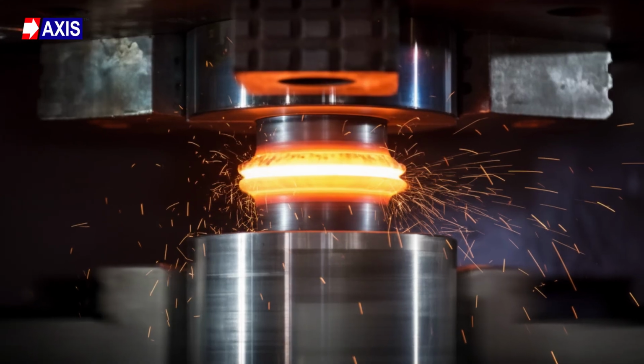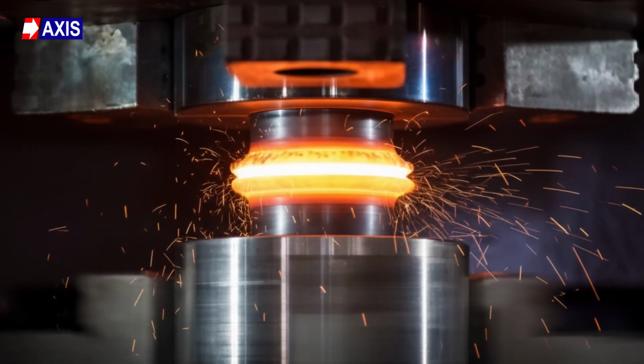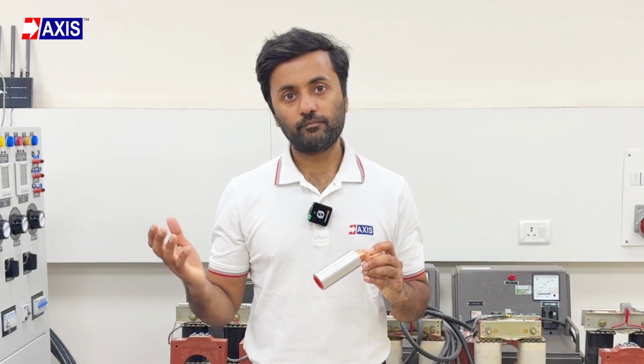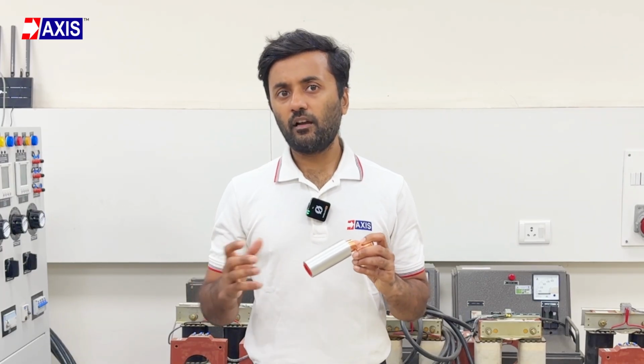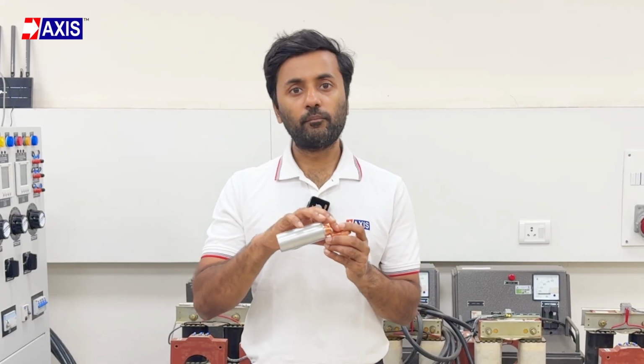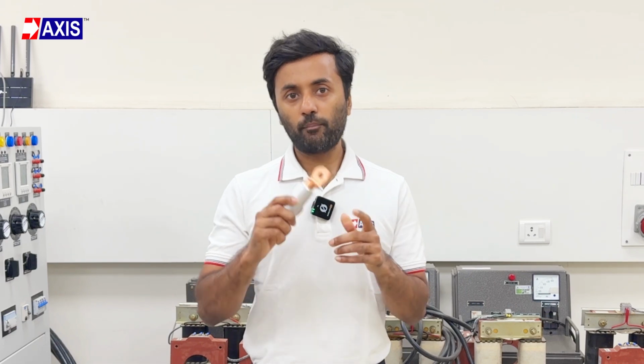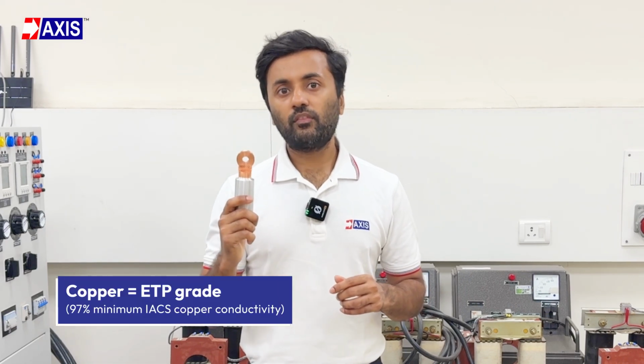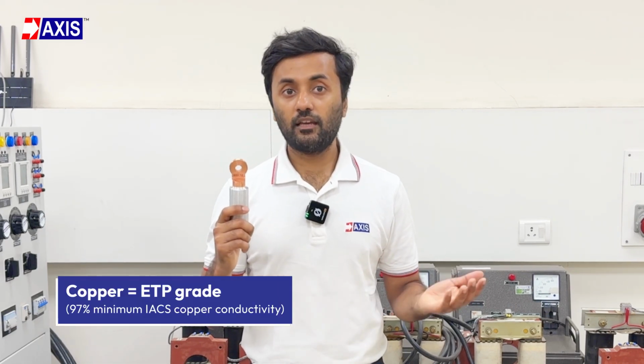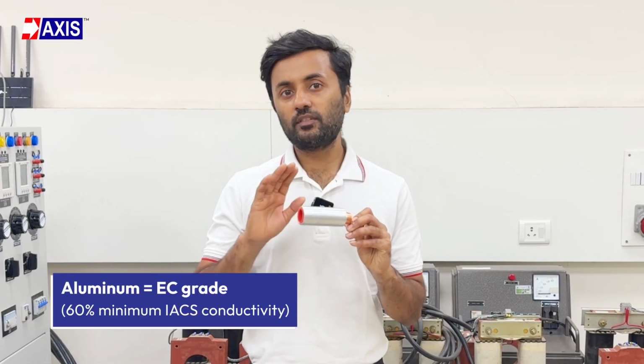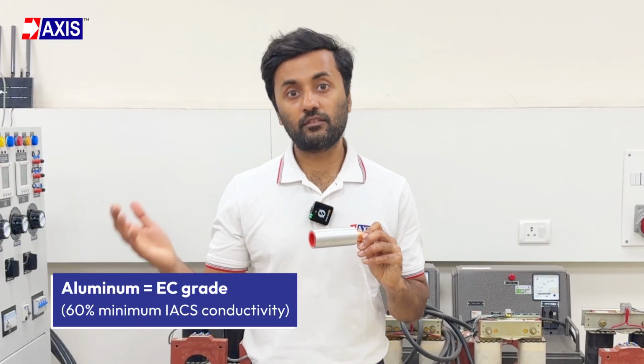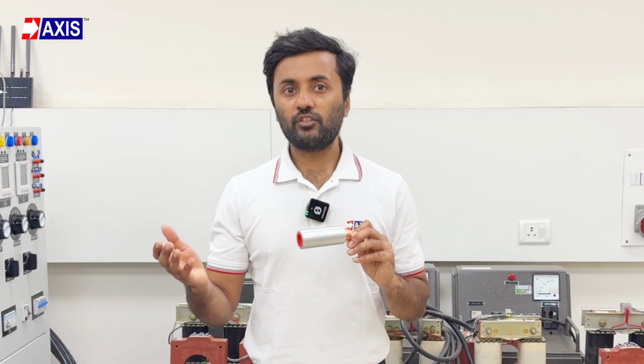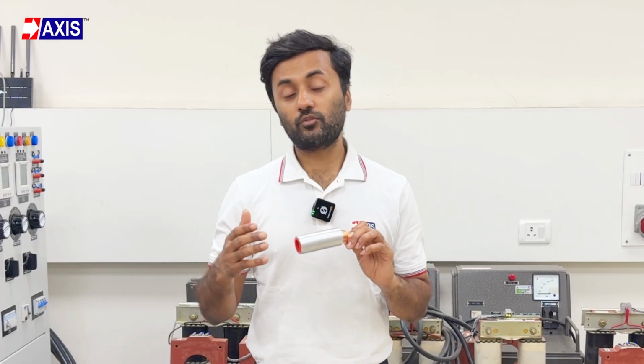Apart from just compliance, your bimetallic lug should be friction welded, which creates a metallurgical bond and prevents corrosion. Since bimetallic lugs are a combination of aluminium and copper, you must ensure that the copper is ETP grade with 97% minimum IACS copper conductivity, and the aluminium is EC grade with 60% minimum IACS conductivity. Avoiding these specifications will compromise the safety of your solar plant.